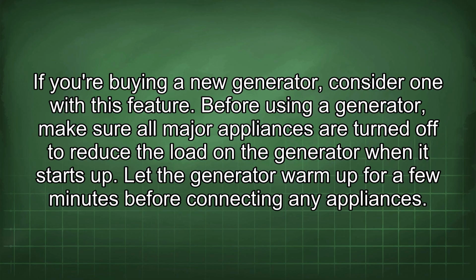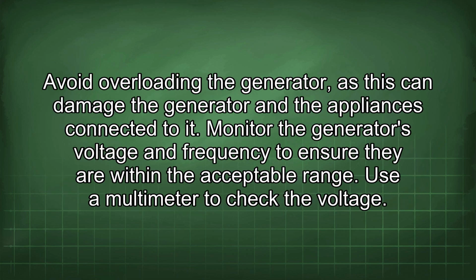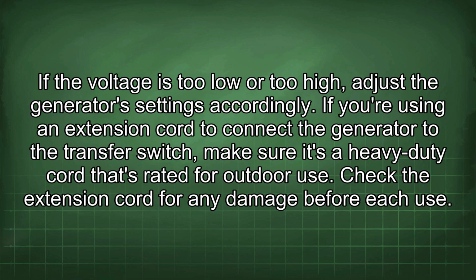Before using a generator, make sure all major appliances are turned off to reduce the load on the generator when it starts up. Let the generator warm up for a few minutes before connecting any appliances. Avoid overloading the generator, as this can damage the generator and the appliances connected to it. Monitor the generator's voltage and frequency to ensure they are within the acceptable range. Use a multimeter to check the voltage. If the voltage is too low or too high, adjust the generator settings accordingly.